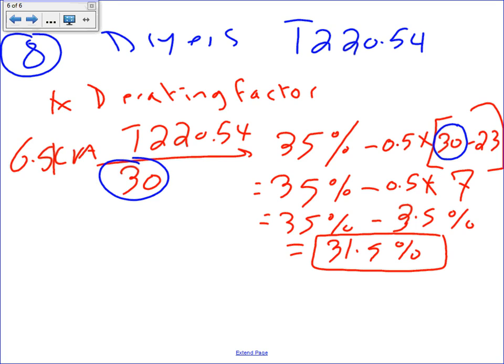Step by step. Are you sure you're not increasing the percentage? You're decreasing the percentage. Yes, that's what they want. The idea, Chris, is the more dryers that you have, the more likely it is that you will not use them simultaneously. So the percentage is less, so you should end up with less than 35. If I have 100 VA and I multiply it by 0.35, oh, okay, so it's the inverse. Yeah, we haven't multiplied yet. We're just finding the derating factor yet.